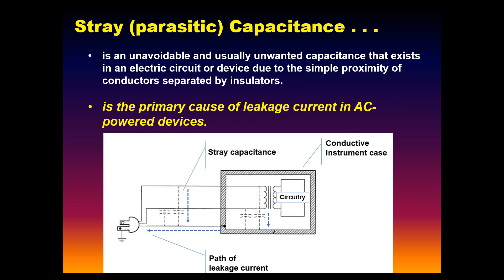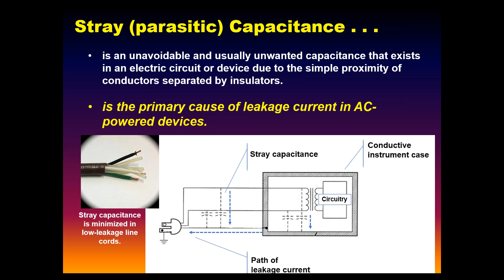Some of you may remember the old blue line cords, made by Dale, really thick, big, long cords, blue and pink, with much lower leakage current because they had polypropylene fillers inside to separate the distance between conductors. So it had much lower leakage current, though it was a bitch to work with, the plug capsules got bad, and straight leads were different. It was a big, bulky cord, but had lower leakage current, and we kind of knew what was going on. The goal was to try to minimize the stray available leakage currents.